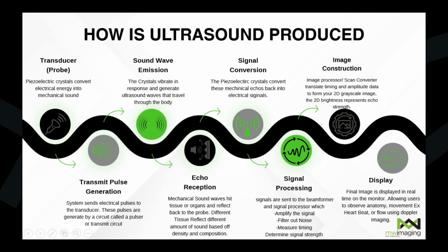These mechanical sound waves hit tissue, organs, and they reflect what we call echo receptions back to the piezoelectric crystal. Once the piezoelectric crystal senses this ultrasound coming back to it, it vibrates again and turns these mechanical signals back into electronic signals. These signals are then sent to the ultrasound system where it completes signal processing. These signals are sent to the beamformer, signal processors. These boards inside the system amplify the signal. They filter out the noise. They measure timing, and they determine the strength of the signal.